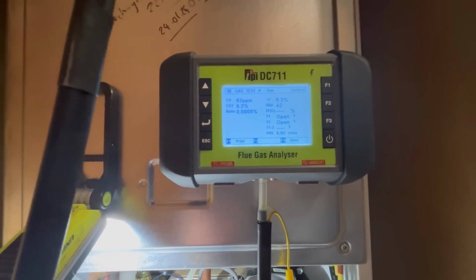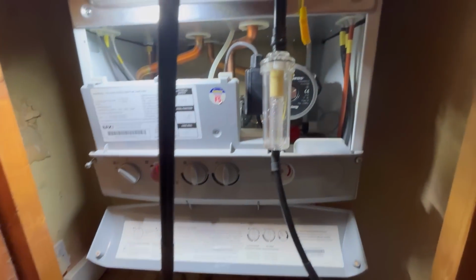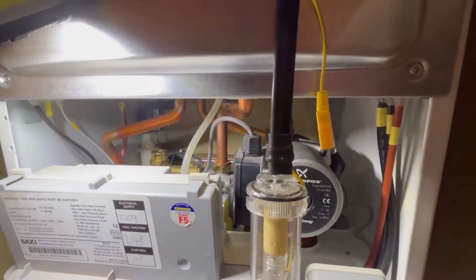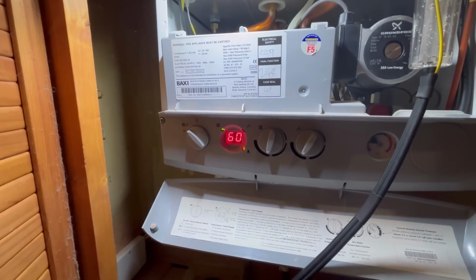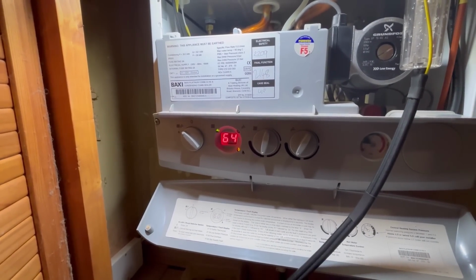Right, so maximum was alright. That's our minimum now. Not been able to make that noise yet, so I don't know whether the gas valve was just slightly out on minimum. Strange one, that. So obviously, when it was in minimum mode, the parts per million would go sky high. Although it was saying 8.5 to begin with when I first started, I thought I'm going to drop that, adjust that minimum setting down again to like 8.2 and just see what happens. And I tried it and tried it and tried it. Kept putting max, minimum, even just turned the heating on its own without having it in service mode, and it seemed to be playing ball. It was modulated down.